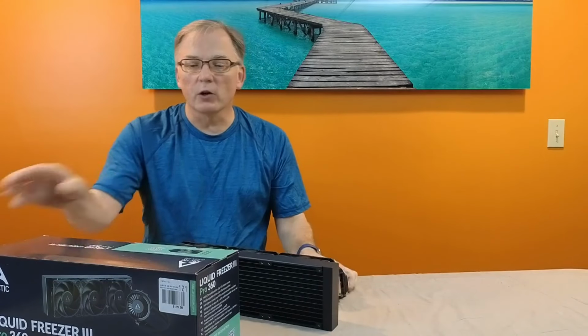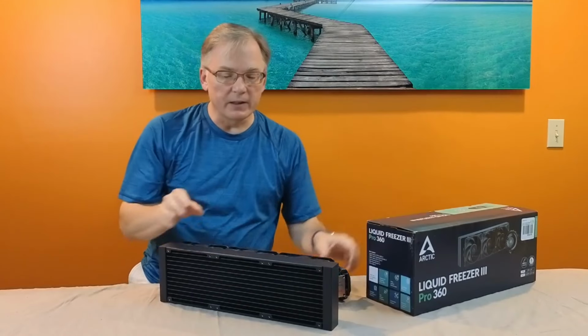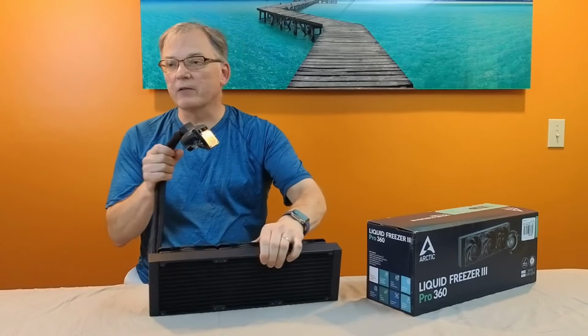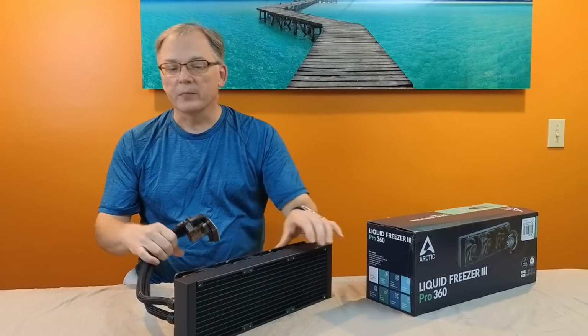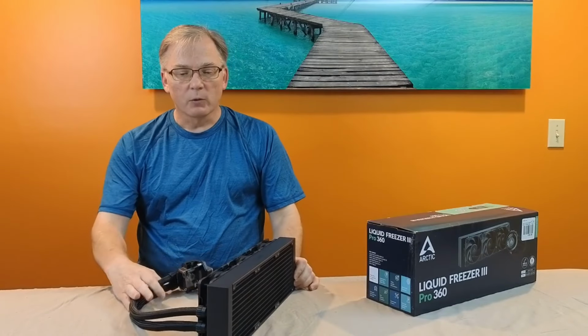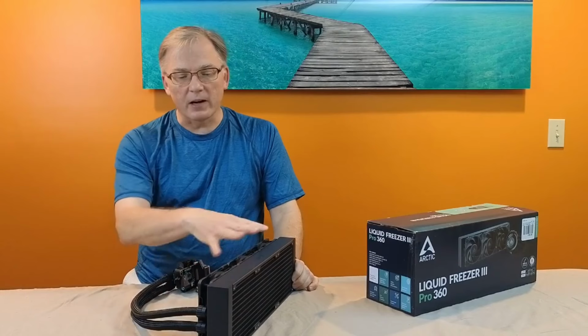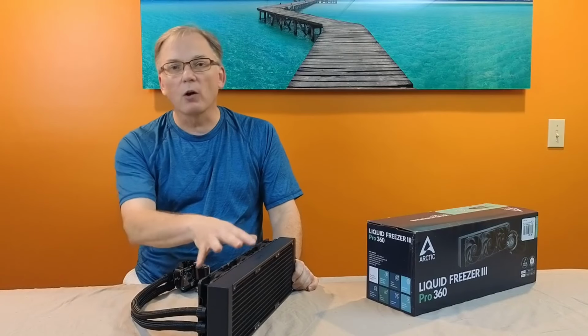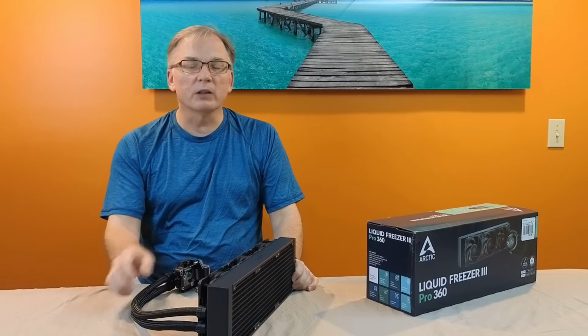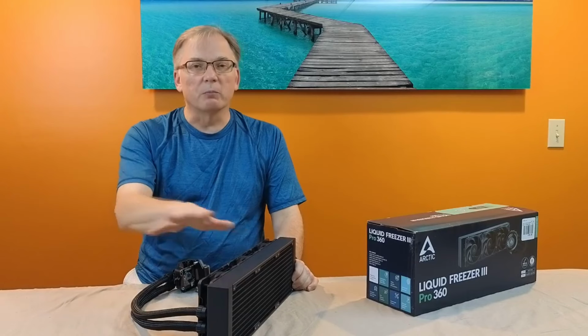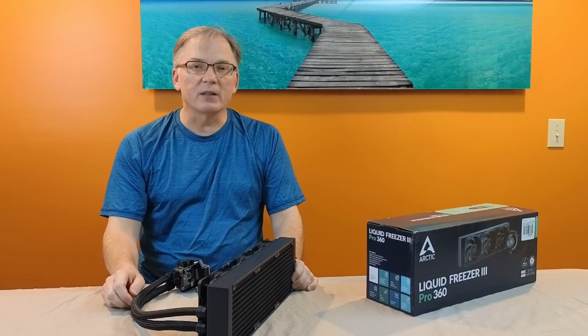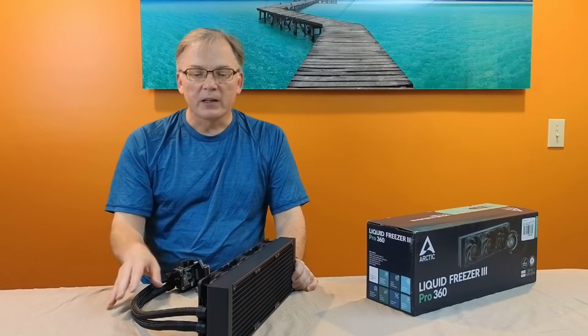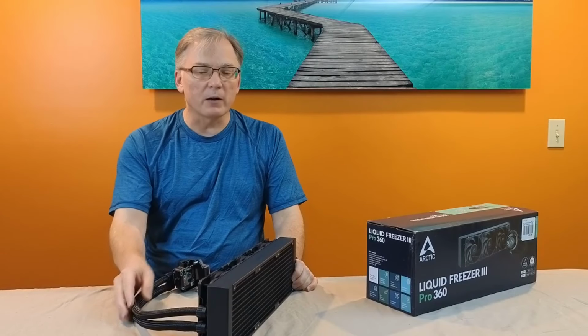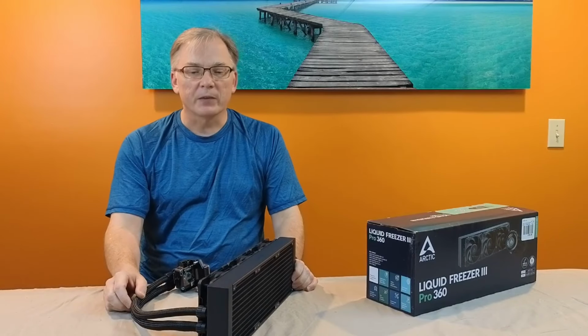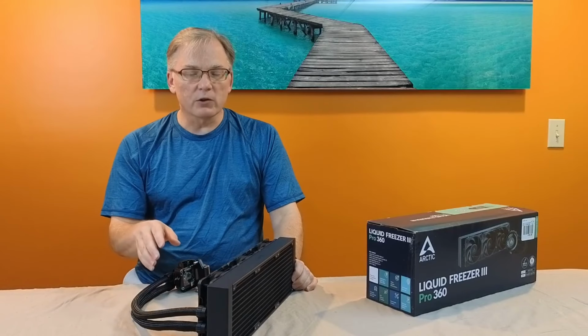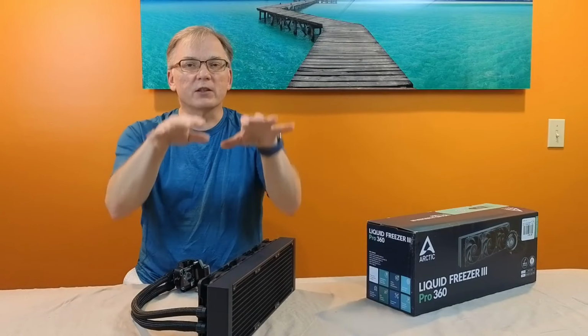One thing I want to note about installing it in the case, which is important for any all-in-one, is that there will always be air in the system. You will never have a case where it's completely full of water and stays that way forever. There will always be some air, either from the manufacturer or developing over time, and you want to make sure all air rises to the highest spot.